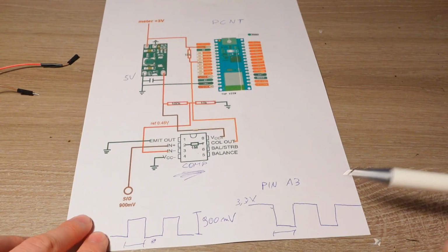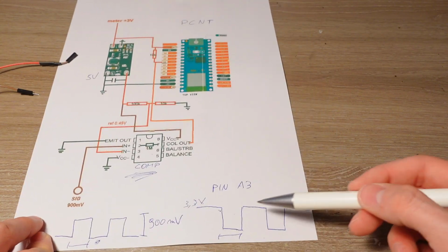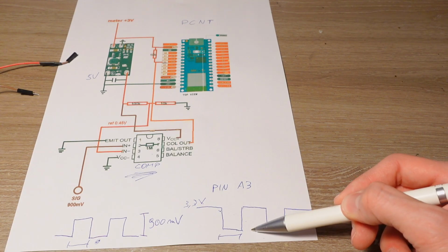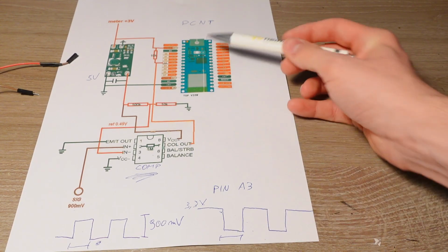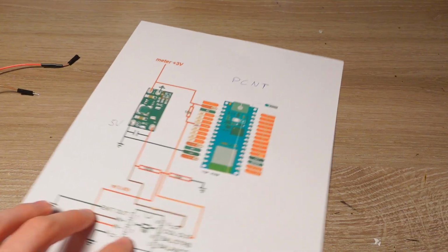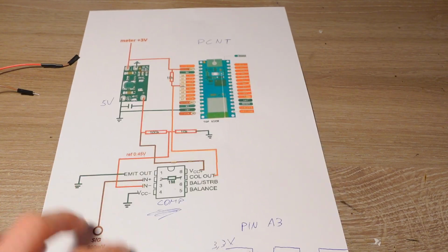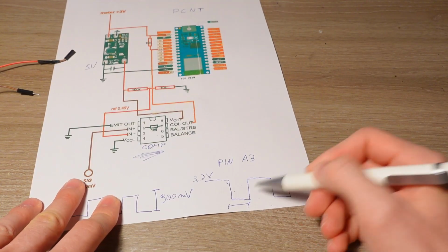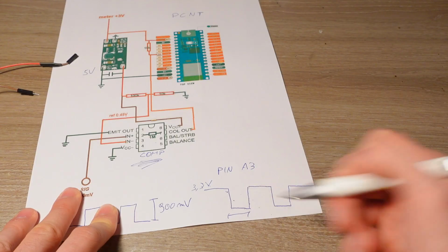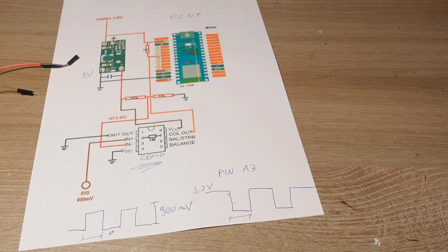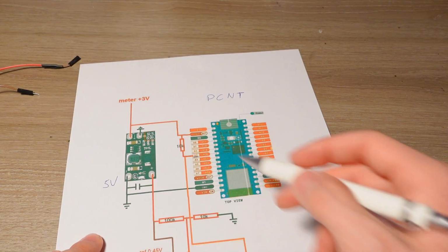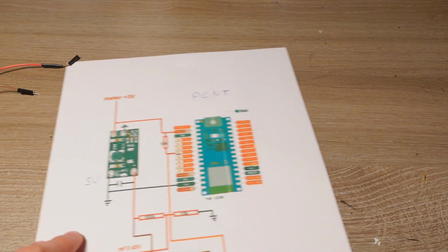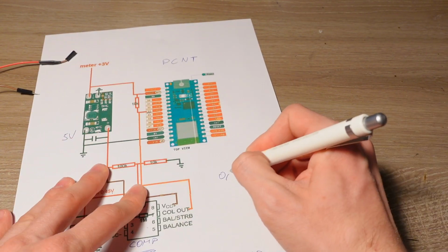It doesn't matter if the pulses are positive or negative at the end, because the pulse counting unit can detect both the rising and falling edge of our pulses, and so you can see either end of the pulses and count it anyway without any problems. Pulse counting unit is refreshed every 0.5 seconds.